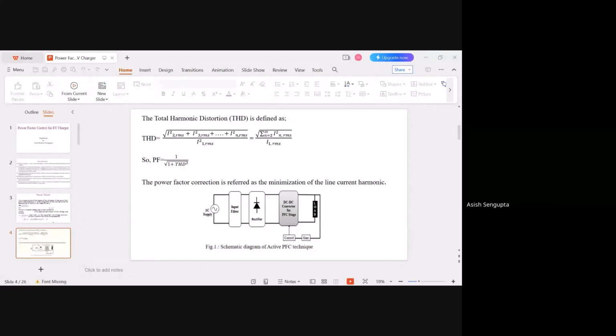Now, as we discussed power factor and voltage distortion, we can see in these particular slides the benefits of a high power factor. Voltage distortion is less, all the power is active, the RMS current is small, and a higher number of loads can be fed. These are the advantages where circuits with a power factor controller are also described, where you can see the cost saving factor: electrical loads like SMPS, electronic ballast units or other electrical loads become much simpler. Similarly, the second advantage we show for the power factor controller is the smaller RMS current, which permits the use of very small and much more cost-effective rectifiers by the manufacturer of the electrical load.